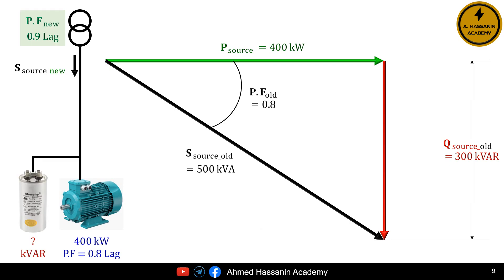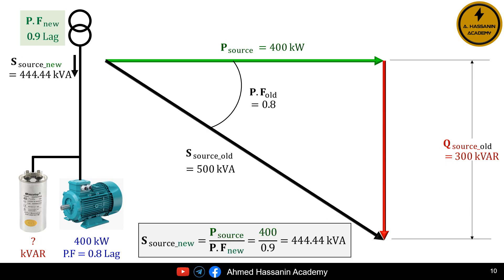Then we must repeat the previous calculations using the new power factor, which equals 0.9. So the total power of the source after installing the capacitor, that is, after improving the power factor, S source new, is equal to the active power P source divided by the new power factor, which equals 400 kilowatts divided by 0.9. Therefore, S source new equals 444.44 kilovolt amperes.